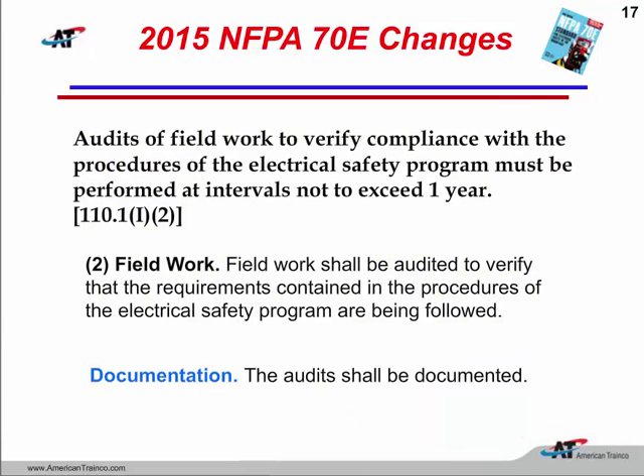Audits. So, generally speaking, our electrical safety program, we have to audit that electrical safety program once every 3 years. But the electrical safety program has a component in there that says field work has to be audited every year. So that cannot exceed 1 year.